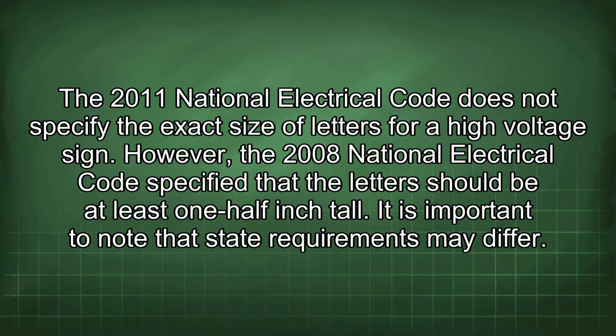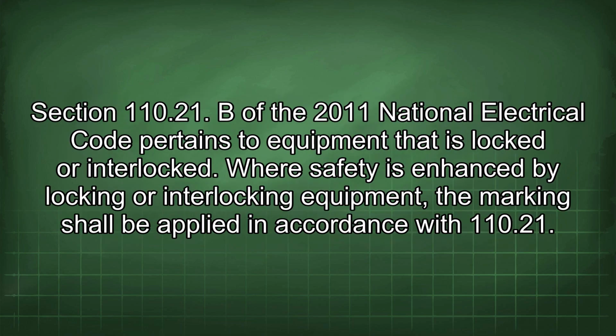The 2011 National Electrical Code does not specify the exact size of letters for a high-voltage sign. However, the 2008 National Electrical Code specified that the letters should be at least 1/2 inch tall. It is important to note that state requirements may differ. Section 110.21(B) of the 2011 National Electrical Code pertains to equipment that is locked or interlocked.